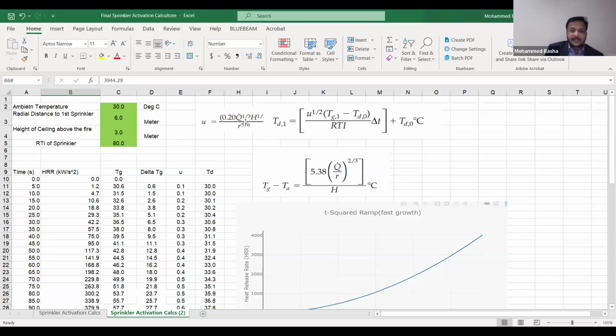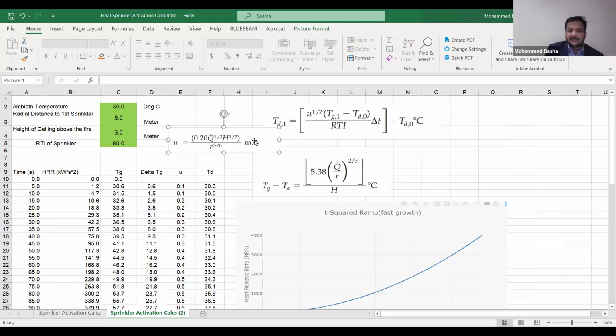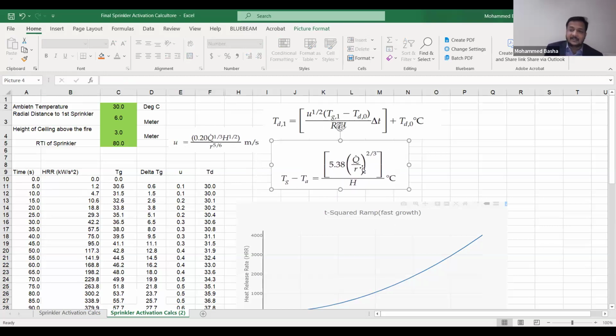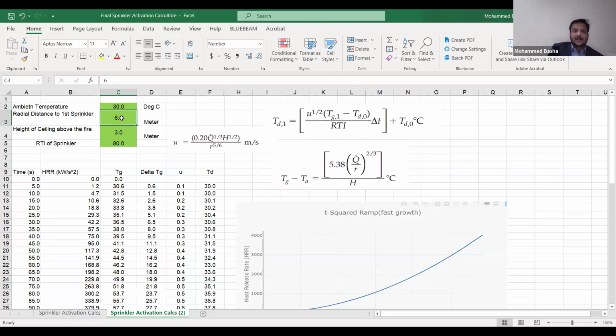So how can we determine this? There are formulas. These are the formulas. This U is called the ceiling jet velocity. This is the heat detector activation time or sprinkler activation time formulas. So what do we need to mention? We need to mention the ambient temperature here, 30 degrees Celsius. Then the radial distance to the first sprinkler. You are going to assume the fire is happening at the middle of the stage. Of course, you will be locating the sprinklers in the ceiling on a 4 meter by 4 meter grid for light hazard, or 3 meter by 4 meter for ordinary hazard, or 3 by 3 for extra hazard. So you can change this value. Now assume we put 2 meters next to the fire. Then the height of the ceiling above the fire. How much is the height of your ceiling?